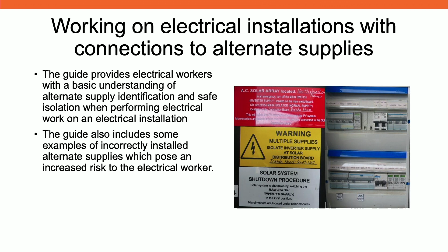So it just gives people an awareness of how to safely operate on those switchboards, because some that we've come across aren't marked appropriately, they're not installed appropriately, and it's easy to get caught out if you turn off the main switch, test that the power's gone, and 30 seconds later an inverter kicks in and re-energises the circuits you're about to work on. So it provides some basic guidance for electrical workers in relation to that.